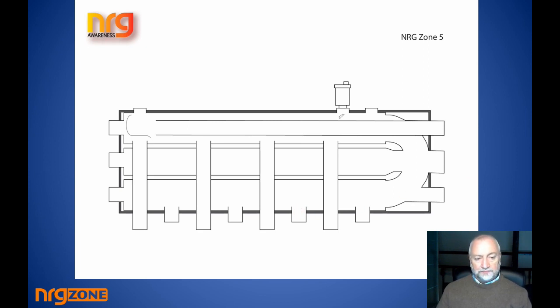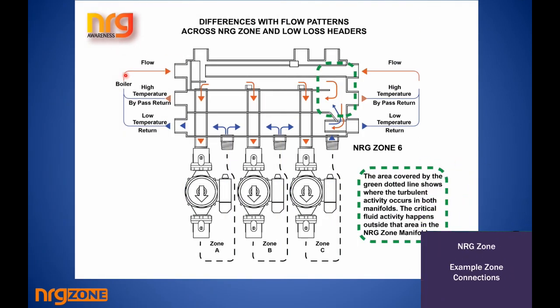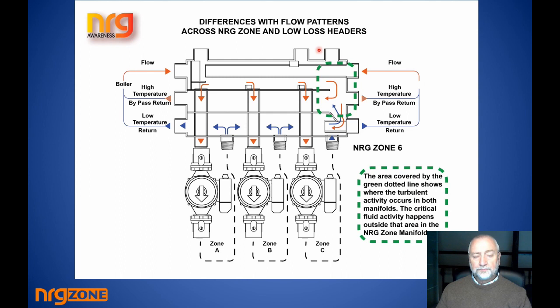So if we move on, we see where the hot water comes in from a boiler, if it's to be piped in this method, and don't take it for granted that this is the only method, because it's certainly not. You can do a lot more. But the normal, ordinary way, the most frequently used way that we come across, would be the flow brought, say, in at the top, and then this first zone will take some of that heated water away, do its heat delivery work, and the return is brought back to the bottom chamber. Likewise, the flow delivers to the second and third pump, so they can take away their respective heat loads and deliver the return water, the coldest water in the system, or the coolest, back to the return chamber, depending on where the heat source is. There is no reason why you can't have a boiler on the left and a boiler on the right. So each zone has an equal chance to get at the heated water.